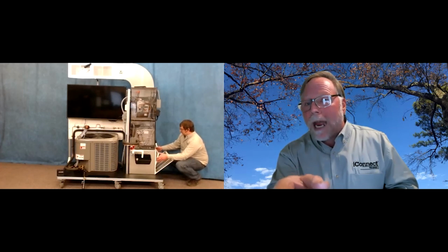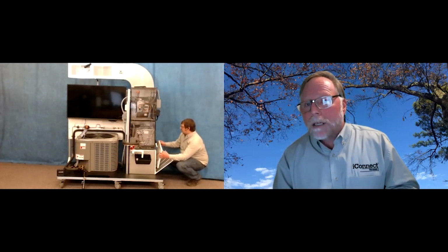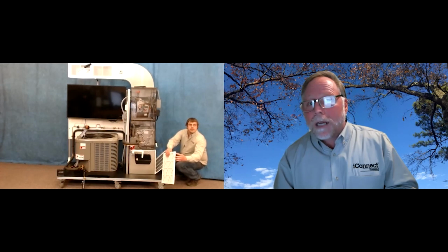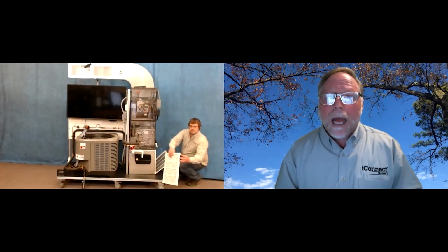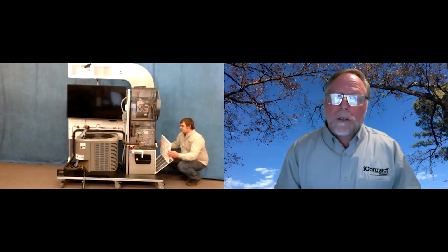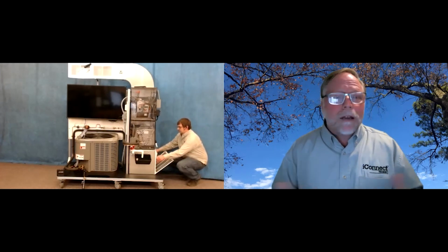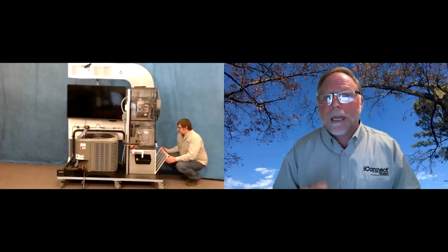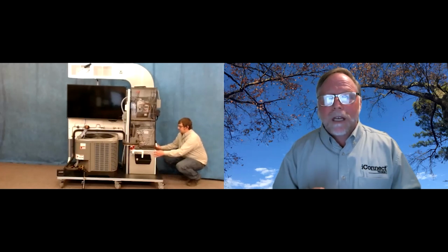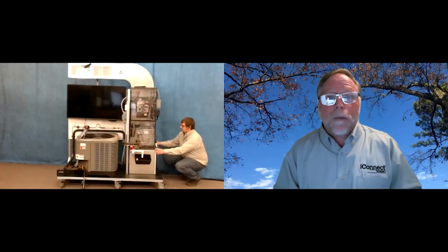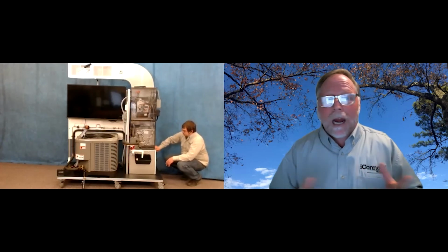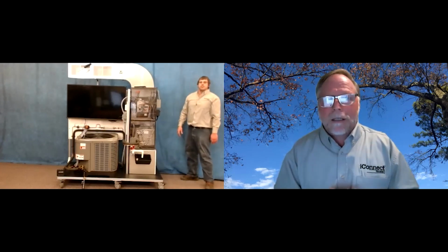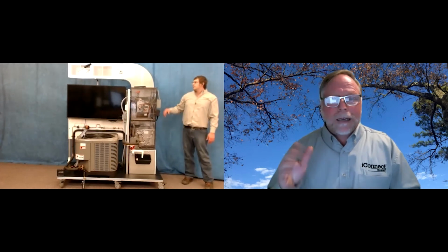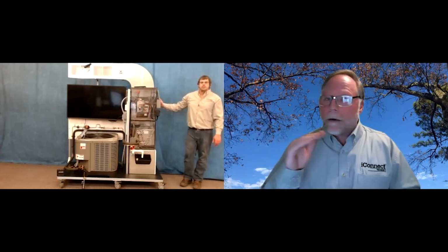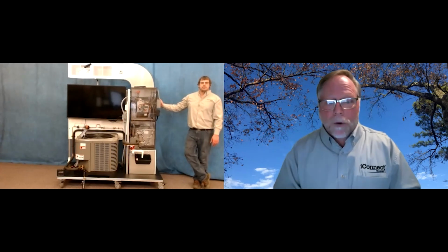Also, Nick, point out the arrow on the filter. And it shows that there is a specific direction that the filter goes. And we can point out that the arrow always goes in the direction of airflow. And then get all kinds of different types of filter and put it in that filter grill. And they can see it affect pressure, they can see it affect temperature, they can see it affect the wet bulb and dry bulb going across the airflow, all kinds of dynamics. A lot of people forget about filters. They think it doesn't matter, just put one in and go with it. Not true. And there's a great way to prove it.